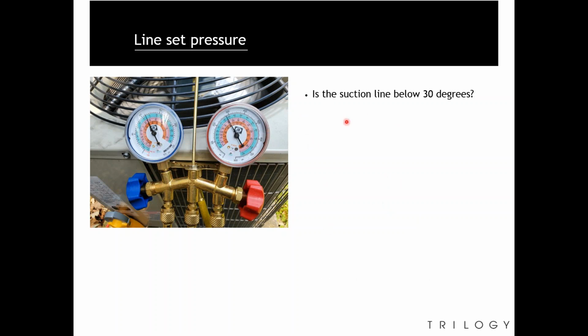So, is our suction line below 30 degrees? 30 degrees saturated temperature will be this inner one in here if we have R22, so it's the inner ring. If you're below 30 degrees, the unit is low on charge and it will probably freeze up pretty quickly.